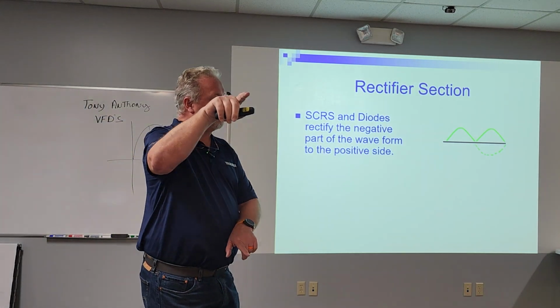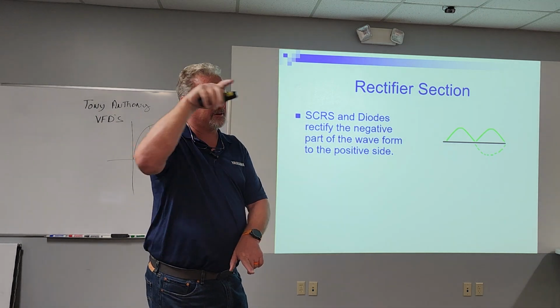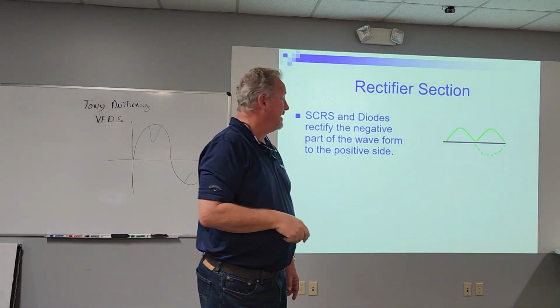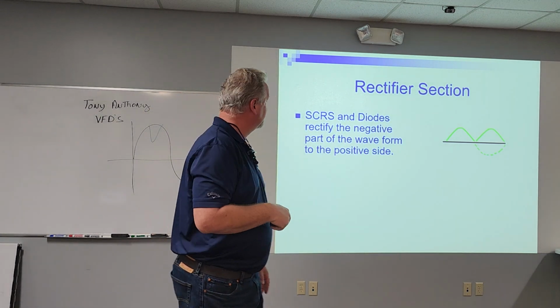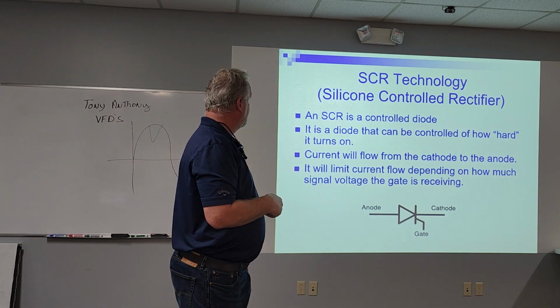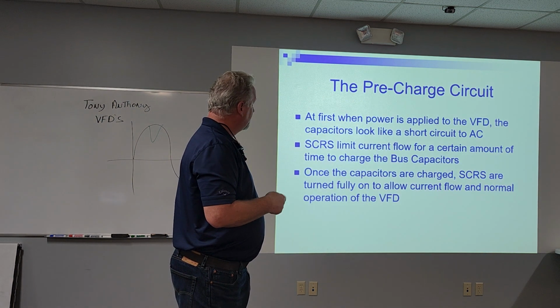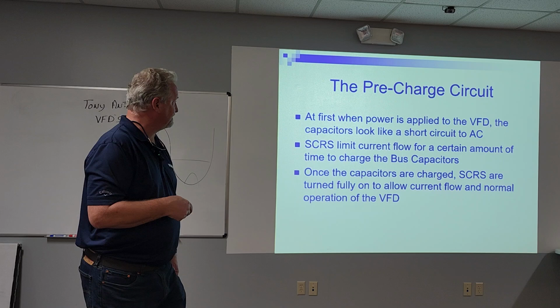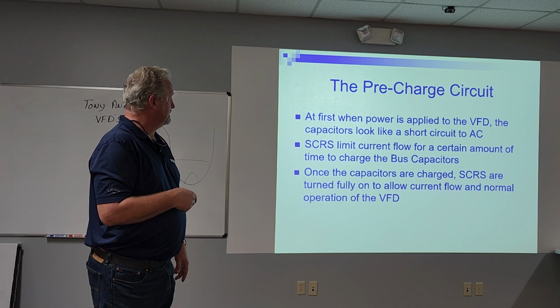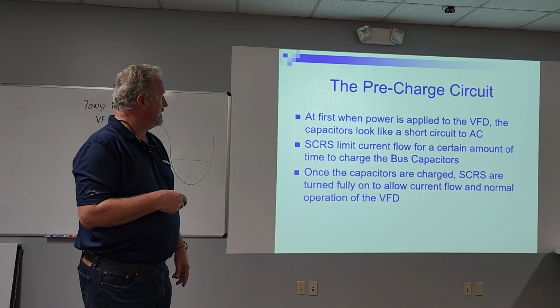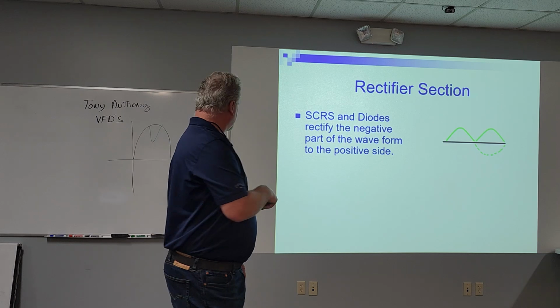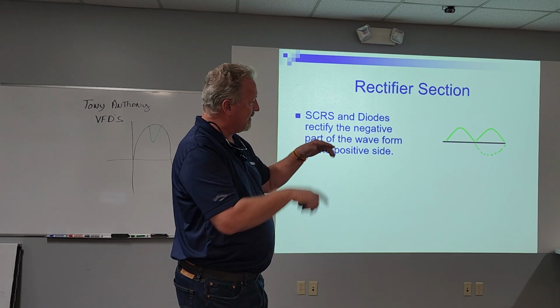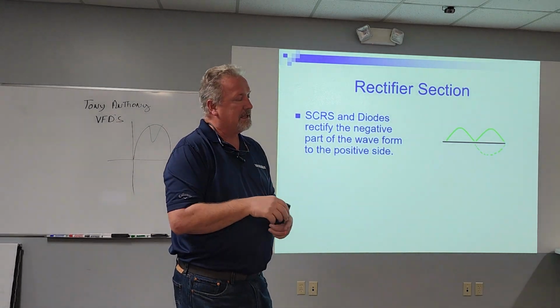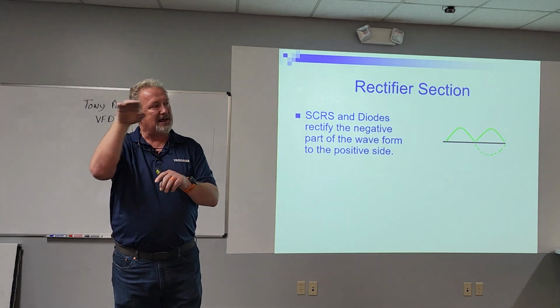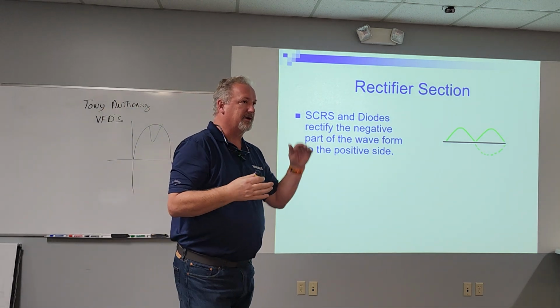When we want to make that a flat line, we don't want those ripples on that DC bus. Get too many ripples, that's going to cause a problem. We'll skip that. Pre-charge relay, we already discussed that. So this is what we're talking about. We take power off, we're rectifying it, and we get a little ripple. Now that ripple, we want that to be a flat line.